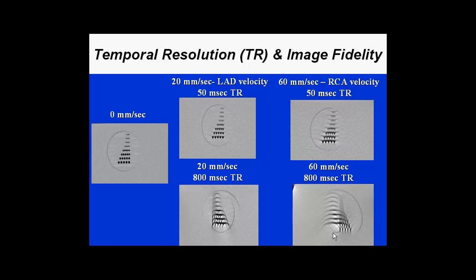These are examples of resolution phantoms at different velocities. On the far left, this resolution phantom has smaller and smaller holes, and we can resolve nearly all of them very nicely — this is without motion. The next panel shows the phantom moving at approximately 20 millimeters per second, which is roughly the peak velocity of the left main and proximal left anterior descending during cardiac imaging. At a 50-millisecond temporal resolution, you can still resolve each of these individual characteristics very nicely. However, at 800 milliseconds — typical of four-slice cardiac CT scanners — there is considerable motion blur.